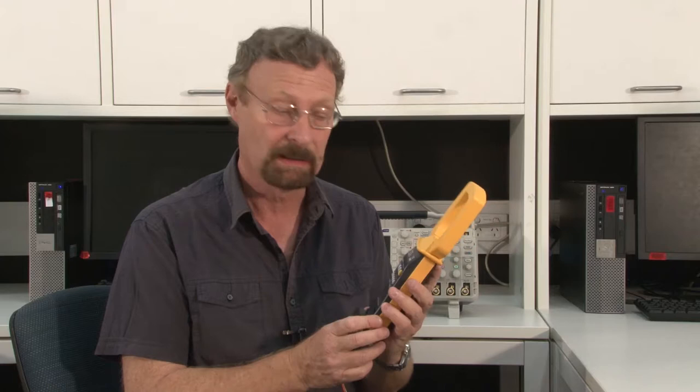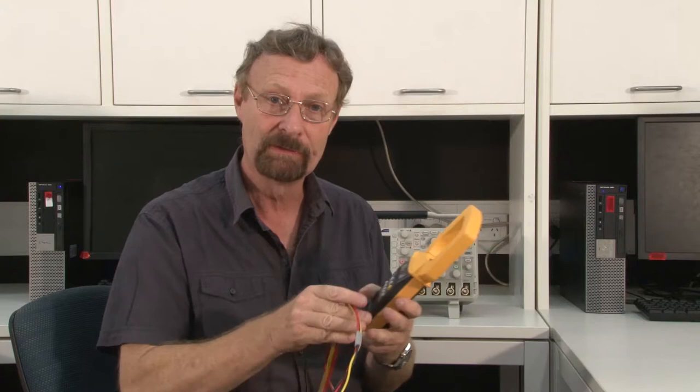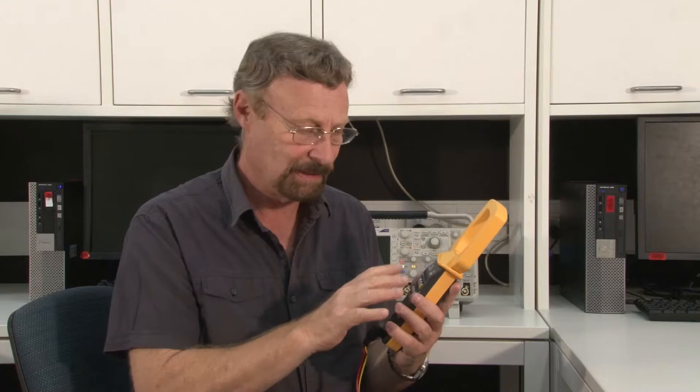It's capable of making measurements of currents up to 1000 amps and voltages up to 600 volts. It's a clamp-on device, so when we're measuring the current we simply clamp around the cable, and these leads are used for making the voltage measurement. If we're talking about a single phase, then we're typically using the black and the red lead.